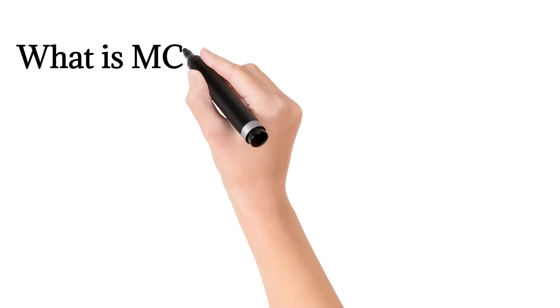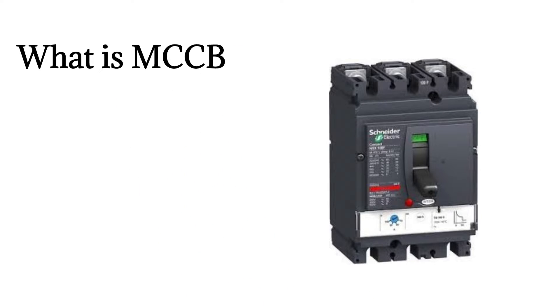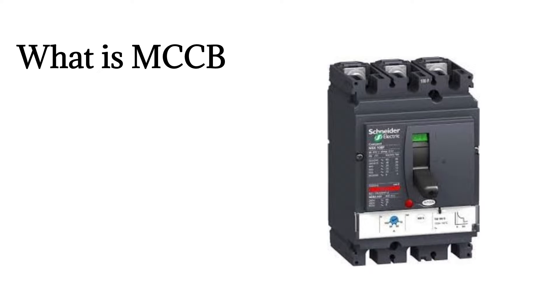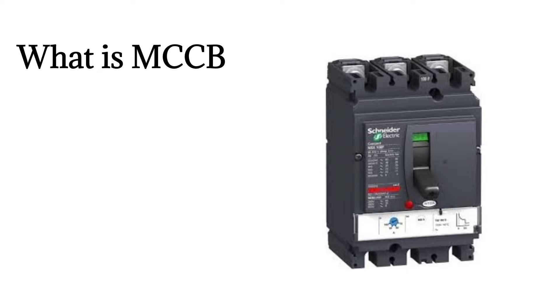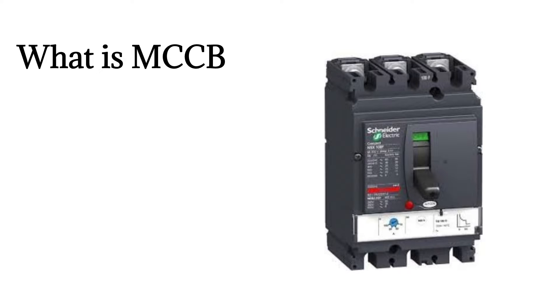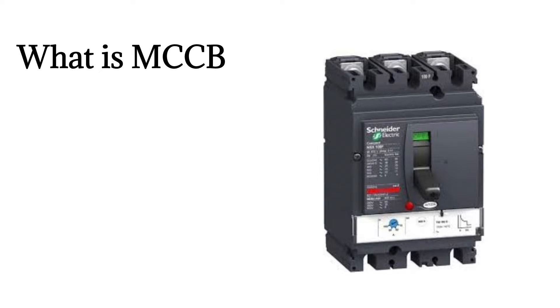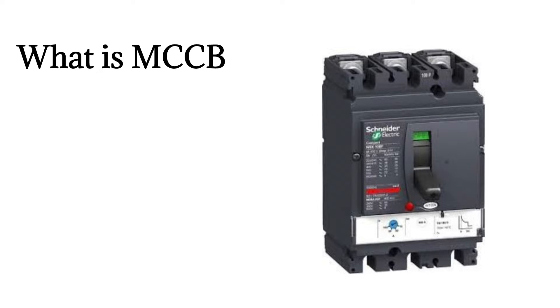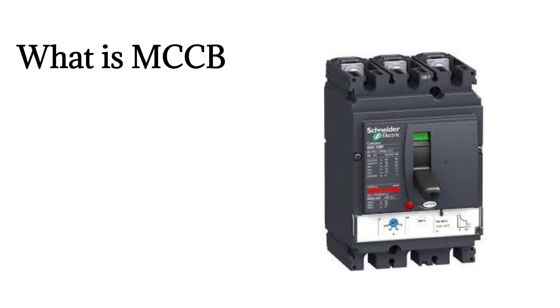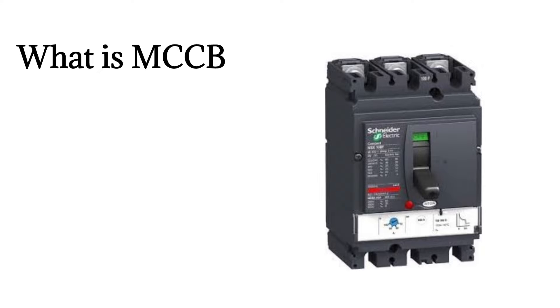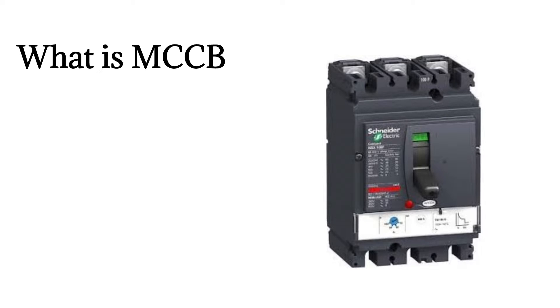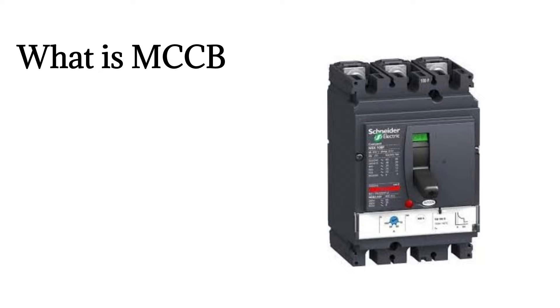What is MCCB? MCCB stands for Molded Case Circuit Breaker. It is another type of electrical protection device which is used when load current exceeds the limit of a miniature circuit breaker. The MCCB provides protection against overload and short circuit faults, and is also used for switching circuits. It can be used for higher current ratings and fault levels even in domestic applications. The wide current ratings and high breaking capacity in MCCB find their use in industrial applications. MCCB can be used for protection of capacitor banks, generator protection, and main electric feeder distribution.